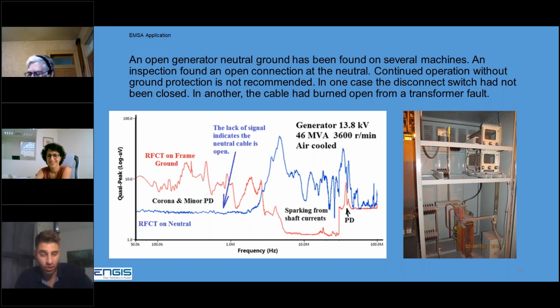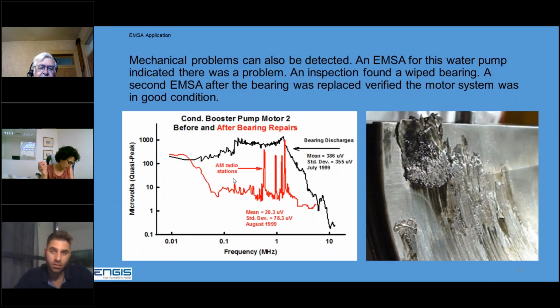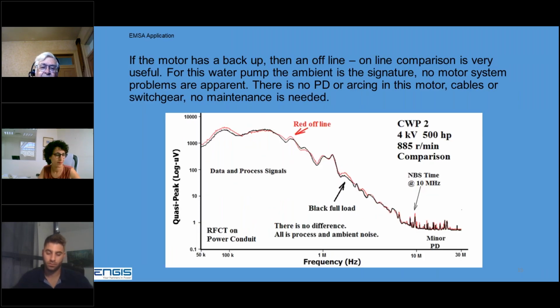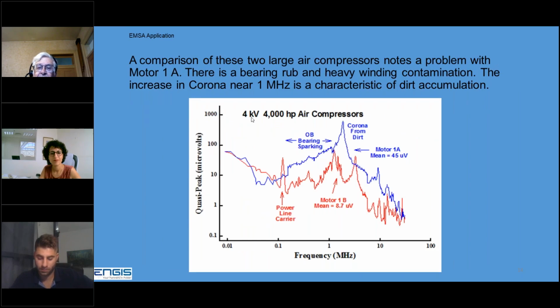Okay, and another question. Is the EMI good for repair job confirmations, the quality of the repair jobs, as well as the fault detection? Well, yes, that was the reason for this example here. This is a large motor. We found a bad bearing, they repaired it, and the curve changed dramatically. So yes, that is one thing you can do with this. I've been amazed that with partial discharge analysis, they've never done that. And of course, that can be done with PDA also. EDF in France, I'm sure, has written some papers on that. But yes, with EMSA and with the sniffer, you can tell that you've corrected the problem. You clean this motor up and then that will disappear. So, yes.